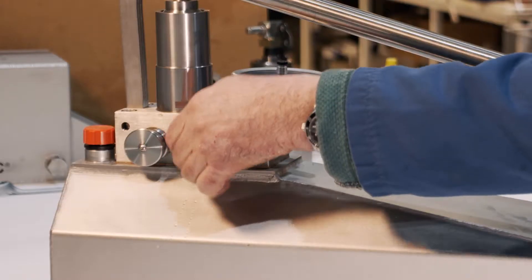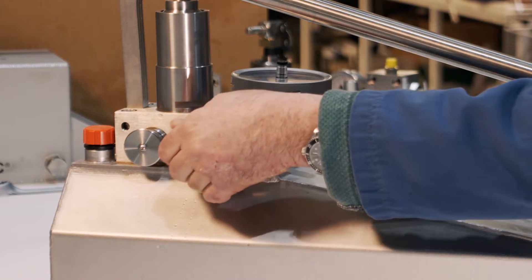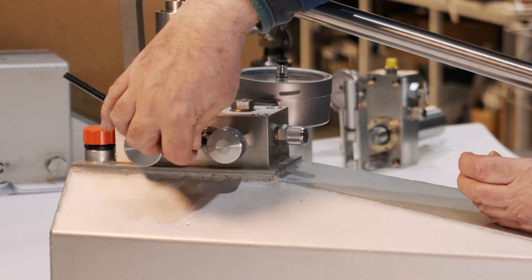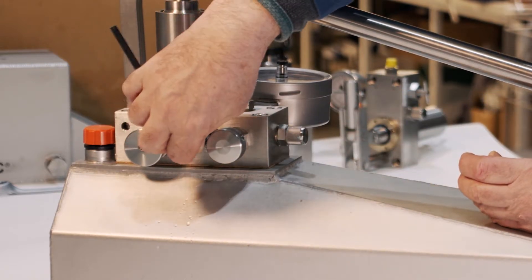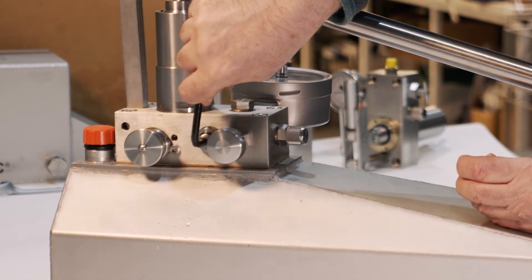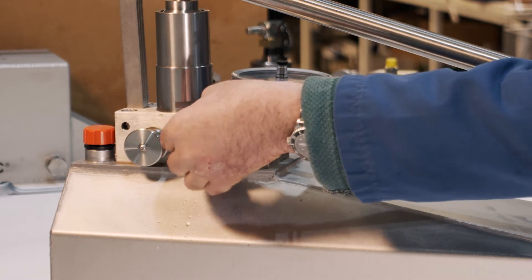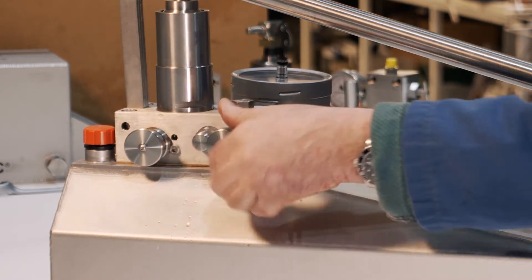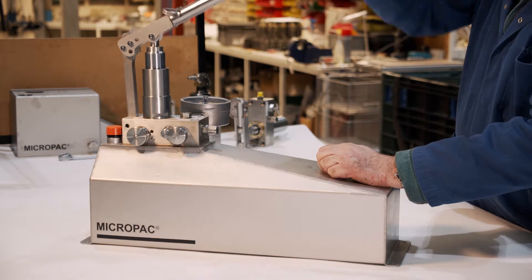Release the pressure. Take the dust cap off. Don't go crazy with adjusting it, just a few degrees because you don't want to ram the plunger into the seat. Take it round a few degrees. Let's see what it's set at now. Put the cap on again. We don't want air getting into the system. Pump it again.